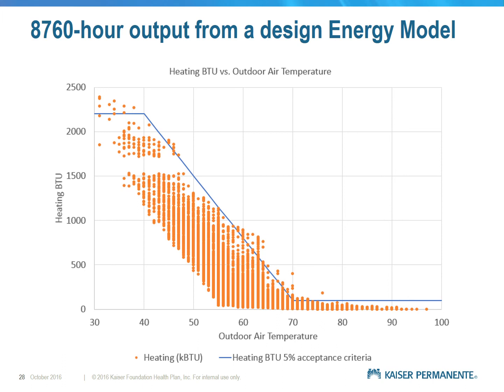So then it falls under the general contractor conditions. In our contracts, we say commissioning issues need to be resolved prior to final completion on the project. So we're putting these into the specs in a section called acceptance criteria before they ever set foot on the job site. That'll make sure that before we hand the building over to the user group, we've tested these systems and we know the energy response to outside air temperature is appropriate and meets the design intent.